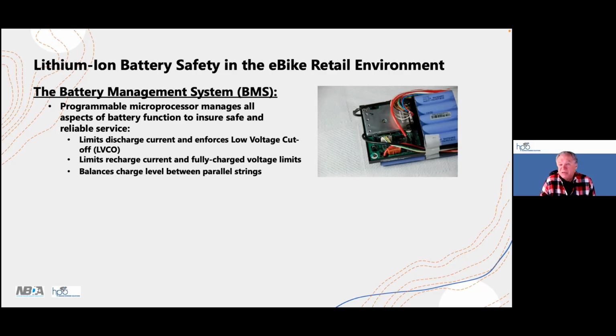Another factor is called cell balancing. We talked about the parallel strings in the battery pack. The parallel strings represent one of the series elements that goes into the pack. If a parallel string is undercharged and the battery is used, that parallel string will be overstressed. So the battery management system measures on a real-time basis the state of charge for each parallel string, and it adjusts the charging protocols to make sure that each parallel string is within about, I think it's about a tenth of a volt. So you want all of those parallel strings to be at approximately the same voltage so as to not overstress a parallel string in service. And that's another function of the battery management system.